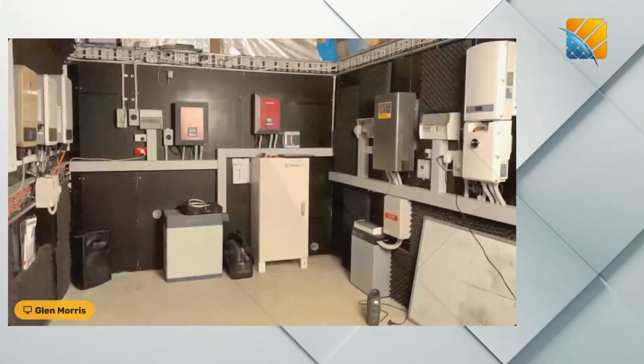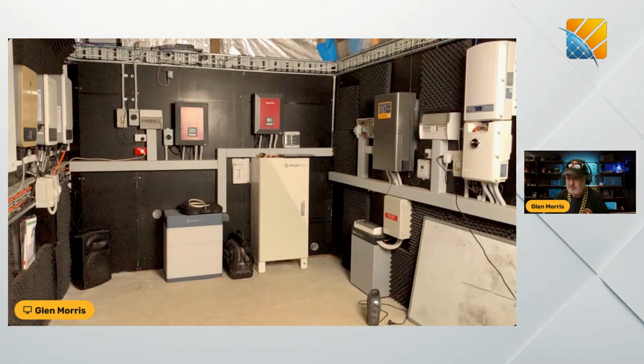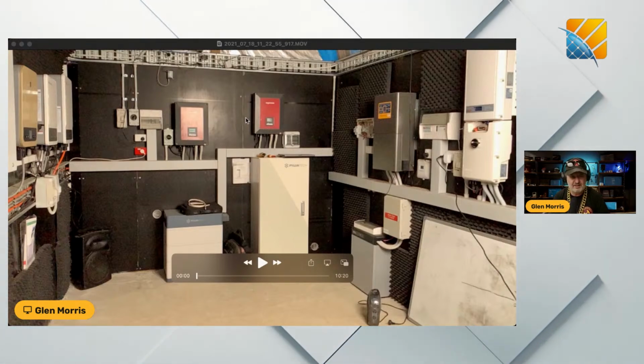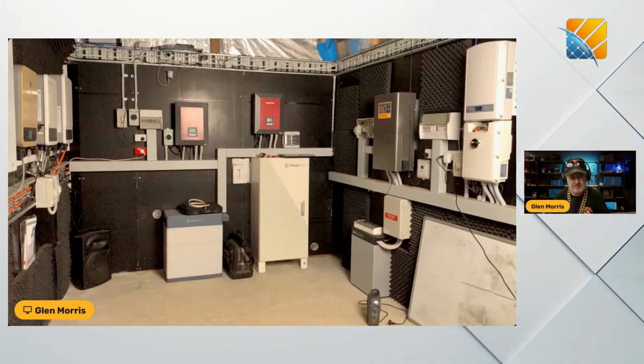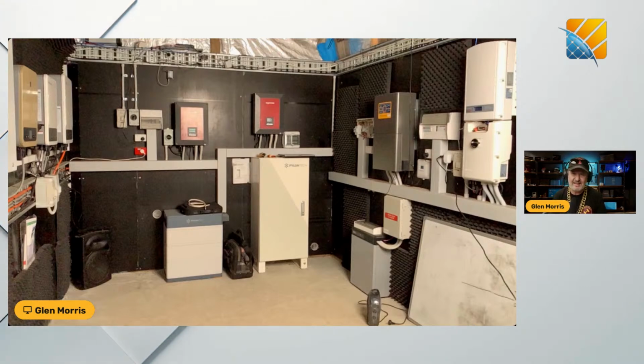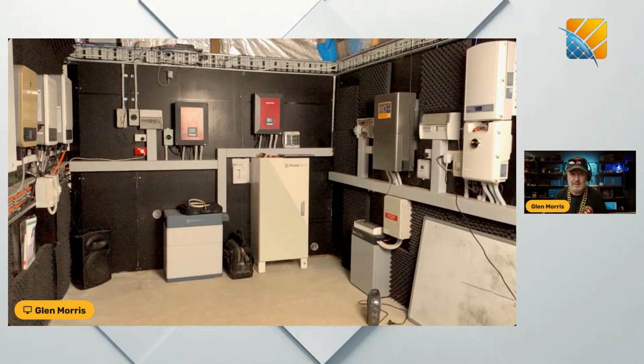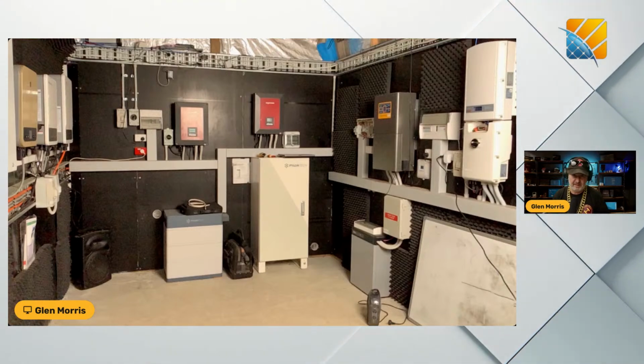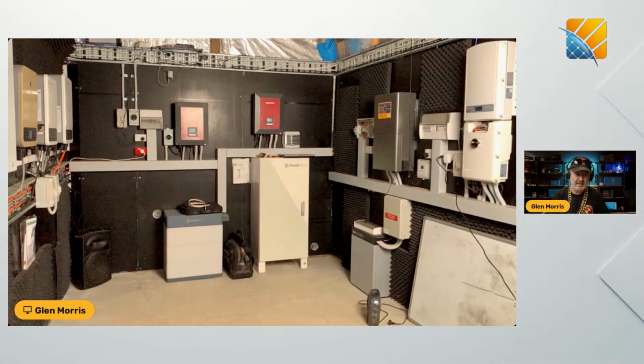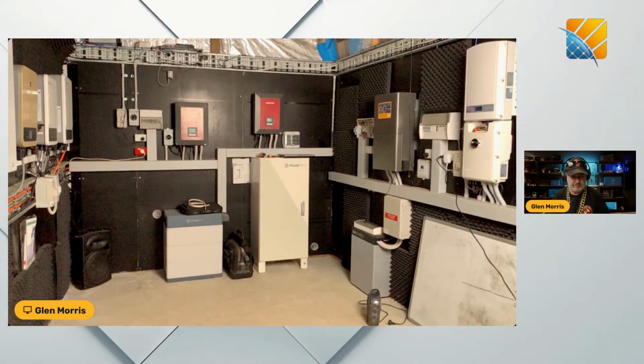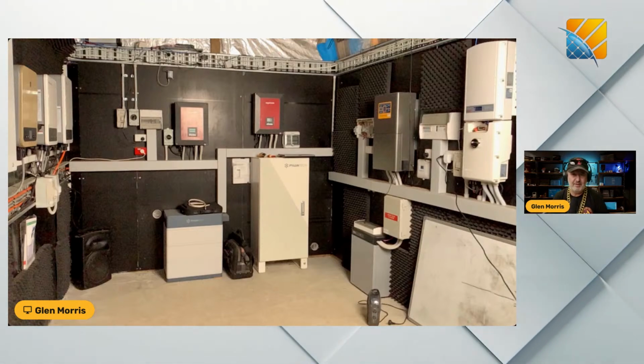Here it is. Sorry for the grainy picture, it wasn't very bright when I filmed this morning. The system you're looking at here is a couple of Ingeteam inverters, these red ones on the wall. There's a lot of inverters in this room, but we'll focus on a few at a time. Those are Ingeteam inverters, a Spanish company. They're 6 kilowatt hybrid inverters, but actually designed as an off-grid inverter primarily that can take PV as an input, take a battery, and take an AC source like a generator or the grid, plus a dedicated AC output. It's got all the bells and whistles you'd need, all in one box, which is nice, and it can be used on grid or off grid.